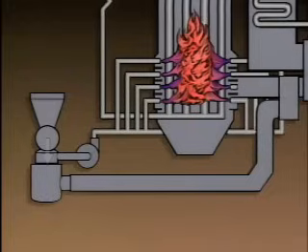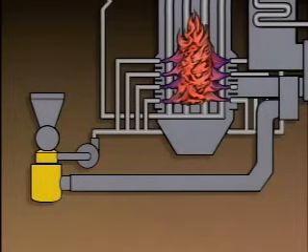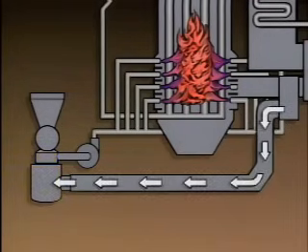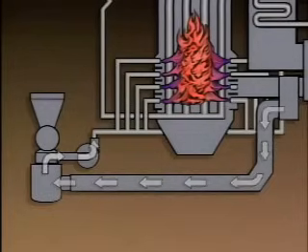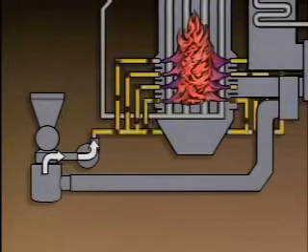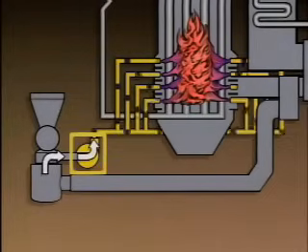Small chunks of coal enter the top of the pulverizer from the coal feeder. In the pulverizer, they are ground into powder-like granules that can mix thoroughly with air. Primary air, which has been heated, enters the side of the pulverizer. The primary air picks up the finely ground coal, dries it out, and carries it to the burners. An exhaustor is used to assist primary air flow from the pulverizer to the burners to help move the coal dust.